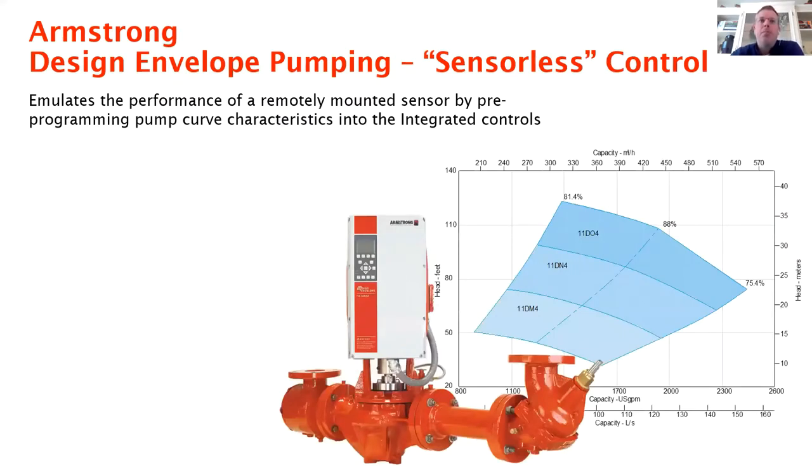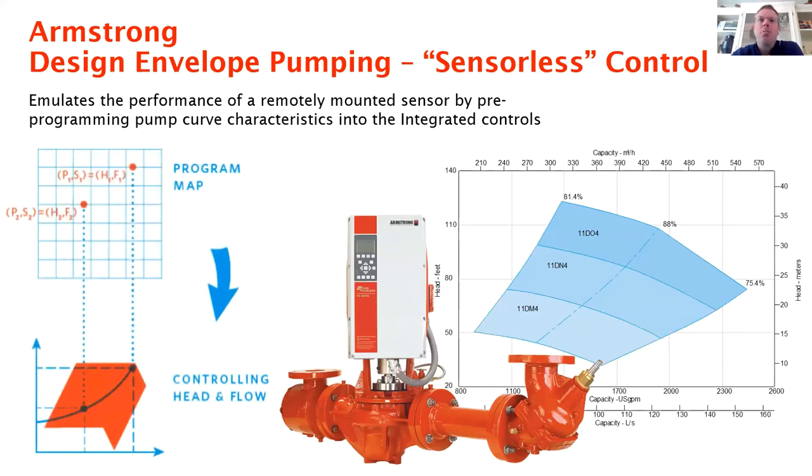So Armstrong has developed their design envelope sensorless control, which emulates the performance of a remotely mounted sensor by monitoring the pump's power consumption and speed, which directly correlates to a specific flow and head. And I'm going to talk about how that's achieved in some following slides.